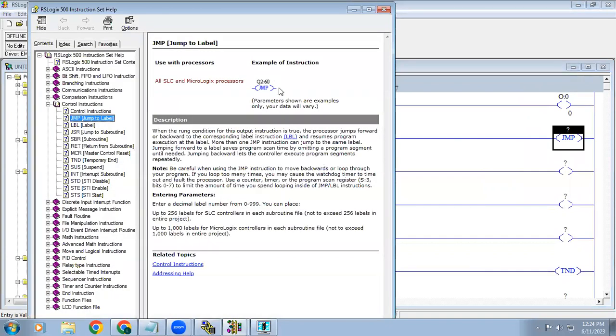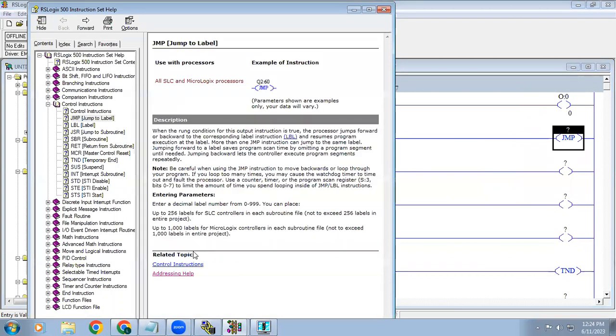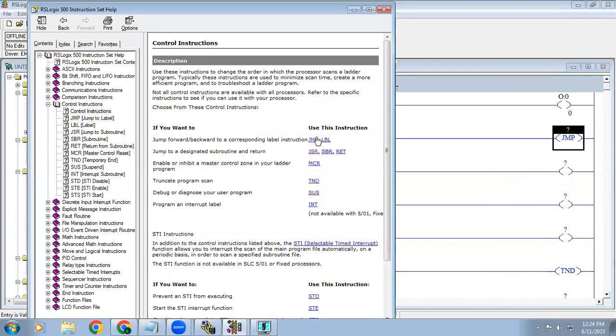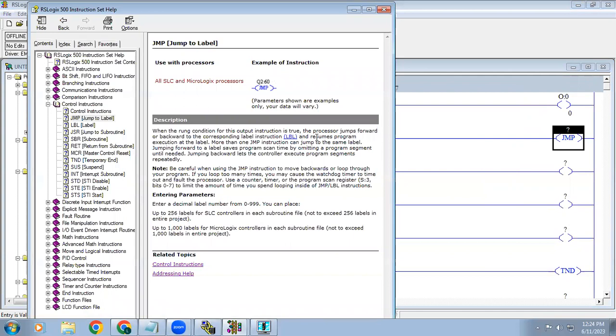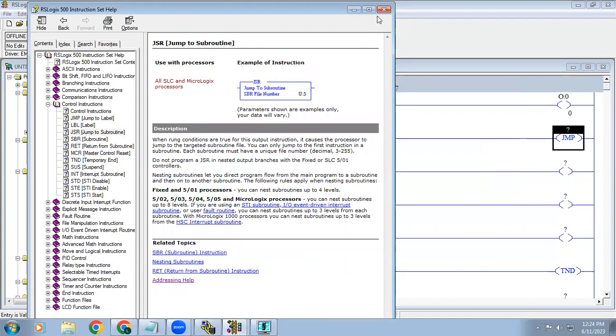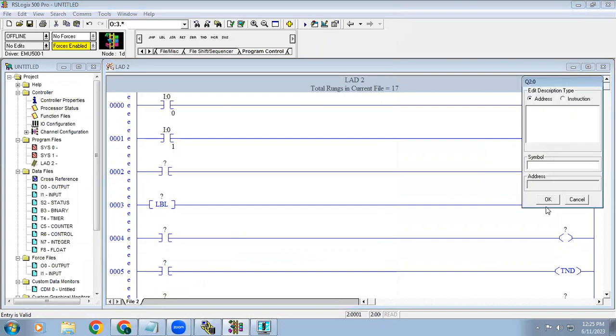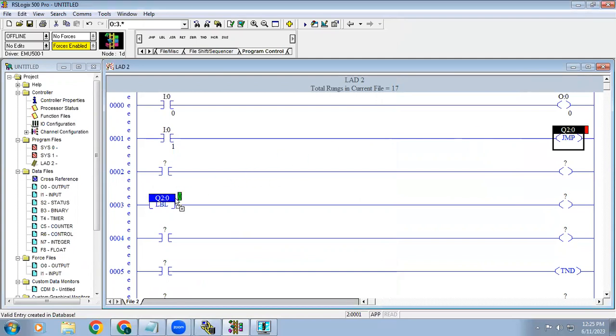In the help you can see the address format. For jump, the address uses Q2 — we have to use Q2 colon format. Similarly, for the label we use Q2 colon. Since this is our first jump, I'm using Q2 colon 0. The same address has to be given in the label as well.